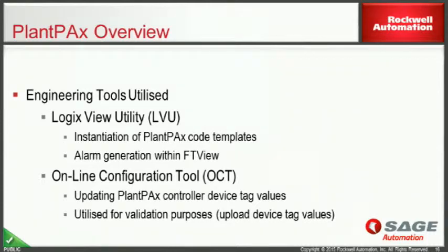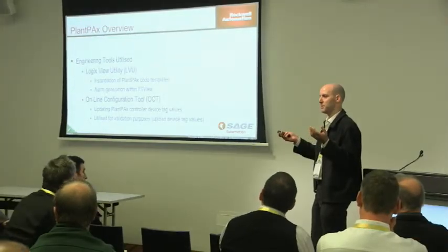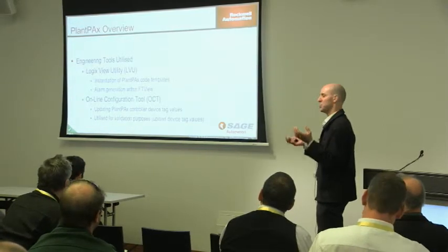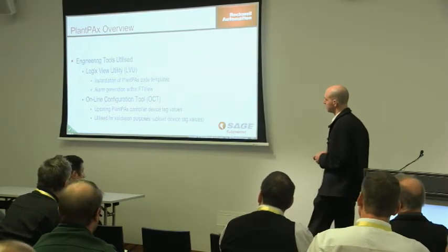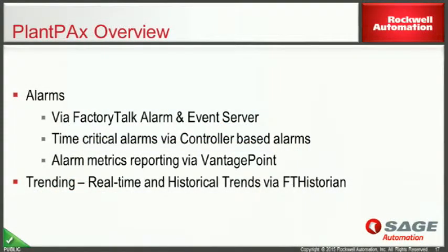The online config tool, OCT, we use for updating PlantPAx controller device tags, and we utilised it for the validation purposes. We uploaded device tag values into test sheets and device test sheets and things like that. That was a very handy tool. Alarms were provided by a FactoryTalk Alarm Event Server. Time-critical alarms were implemented via controller-based alarms. And alarm metrics reporting was provided via Vantage Point out-of-the-box alarm reports. Trending was implemented via real-time and historical trends via FactoryTalk Historian.